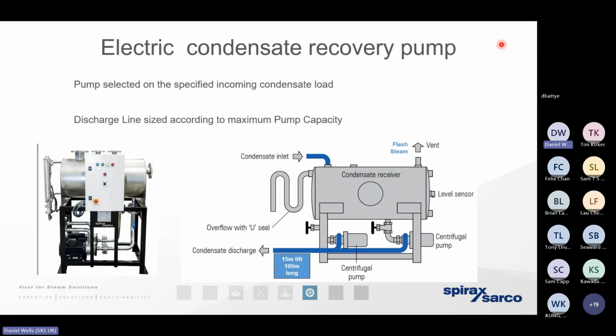Alternatively, we could use an electric condensate receiver. We do need electrical installation, and those electric centrifugal pumps can only move condensate when it's a single phase non-compressible fluid. Any steam that's present, or if condensate exists at a higher temperature, it will result in cavitation and failure. When that happens, the condensate is going to back up and be discharged to waste down those overflow pipes, and we're losing a significant amount of energy. So our cost of steam, gas, and our carbon emissions are going to increase significantly.